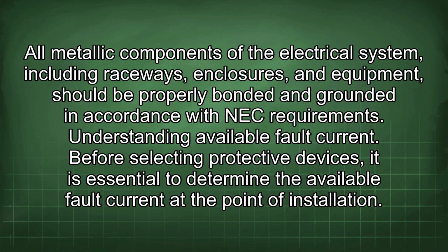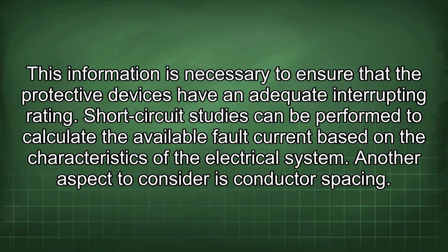Understanding available fault current. Before selecting protective devices, it is essential to determine the available fault current at the point of installation. This information is necessary to ensure that the protective devices have an adequate interrupting rating. Short-circuit studies can be performed to calculate the available fault current based on the characteristics of the electrical system.